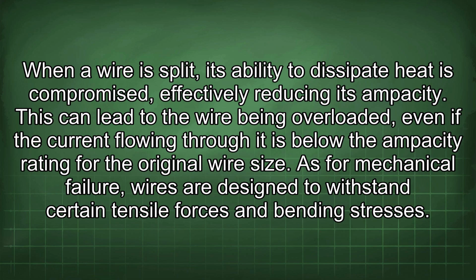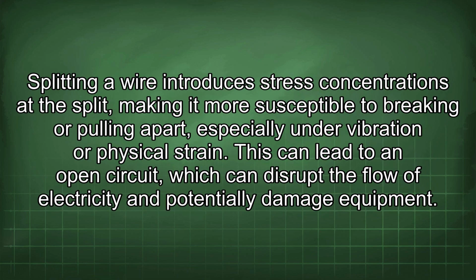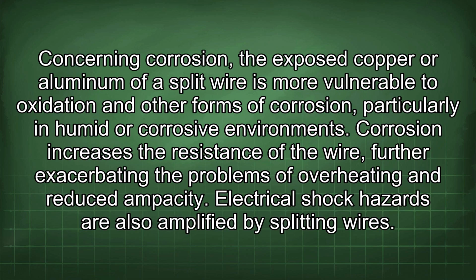As for mechanical failure, wires are designed to withstand certain tensile forces and bending stresses. Splitting a wire introduces stress concentrations at the split, making it more susceptible to breaking or pulling apart, especially under vibration or physical strain. This can lead to an open circuit, which can disrupt the flow of electricity and potentially damage equipment. Concerning corrosion, the exposed copper or aluminum of a split wire is more vulnerable to oxidation and other forms of corrosion, particularly in humid or corrosive environments. Corrosion increases the resistance of the wire, further exacerbating the problems of overheating and reduced ampacity.